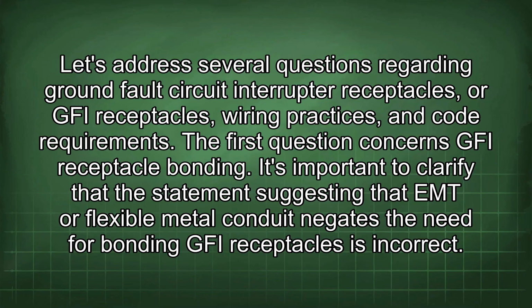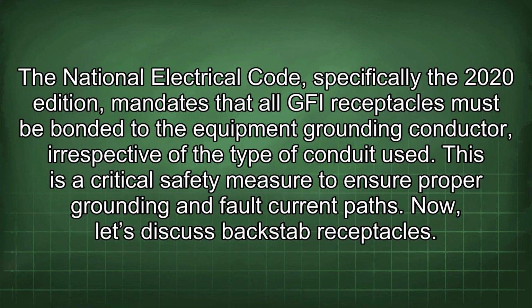Let's address several questions regarding ground fault circuit interrupter receptacles, or GFI receptacles, wiring practices, and code requirements. First question concerns GFI receptacle bonding. It's important to clarify that the statement suggesting that EMT or flexible metal conduit negates the need for bonding GFI receptacles is incorrect. The National Electrical Code, specifically the 2020 edition, mandates that all GFI receptacles must be bonded to the equipment grounding conductor, irrespective of the type of conduit used. This is a critical safety measure to ensure proper grounding and fault current paths.